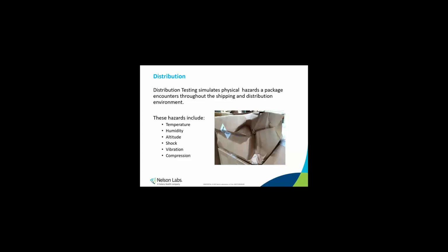Distribution needs to be the first step in the validation because this is where all the damage usually occurs. And as part of the simulation, each hazard is run and the shipper box is inspected after each one. But it's really the damage that's happening on the inside to the sterile barrier system that really matters to us. And that's what we're going to check for in the next validation step.